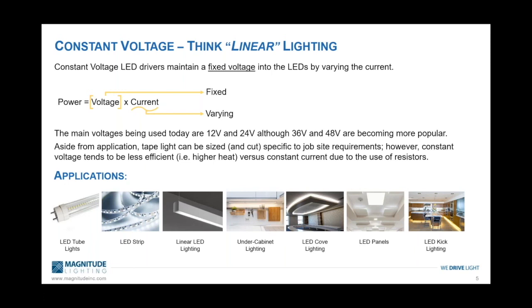The first term is constant voltage. What we like to simplify here is think linear lighting fixtures. In constant voltage, the voltage itself would be constant or fixed, where the current itself could vary throughout the strip. Many voltages you would see in the industry are 12 volt and 24 volt, the most common, but we are starting to see some manufacturers offering 36 and 48 volts. We do have some products that meet those needs as well. So again, with constant voltage, think linear fixtures, tape lighting, linear LED pendants, under cabinet, cove lighting. Those are products that are going to be used with a constant voltage driver. So if you're trying to figure out what driver to use, those are some ideas of applications that use constant voltage.